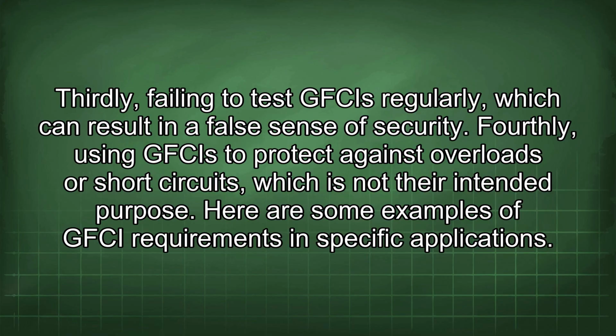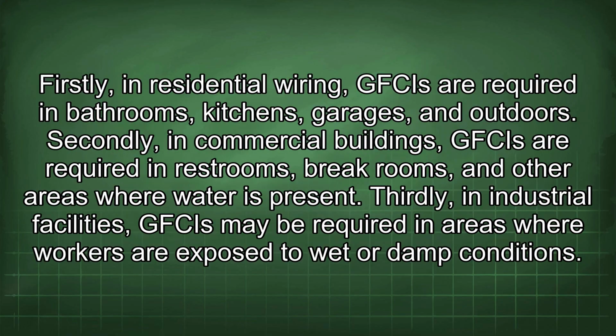Here are some examples of GFCI requirements in specific applications. Firstly, in residential wiring, GFCIs are required in bathrooms, kitchens, garages, and outdoors. Secondly, in commercial buildings, GFCIs are required in restrooms, break rooms, and other areas where water is present. Thirdly, in industrial facilities, GFCIs may be required in areas where workers are exposed to wet or damp conditions.